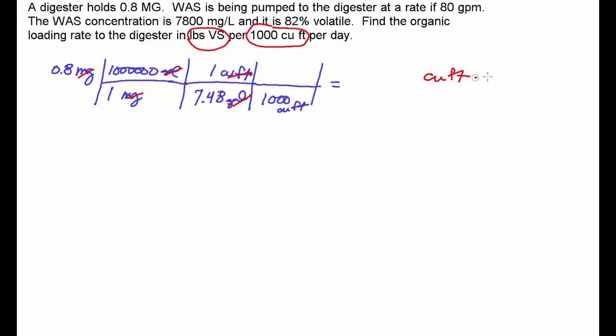So cubic feet times 1,000, essentially, is how that gets written in the books. We've got 0.8 times 1,000,000, divided by 7.48, and then divided by 1,000. So that all works out to 106.95, unless I have fat fingers, which is possible. I would always punch it in twice, and in fact, I think I will, just to be sure. Yep, got the same answer twice, which is always a good indicator.